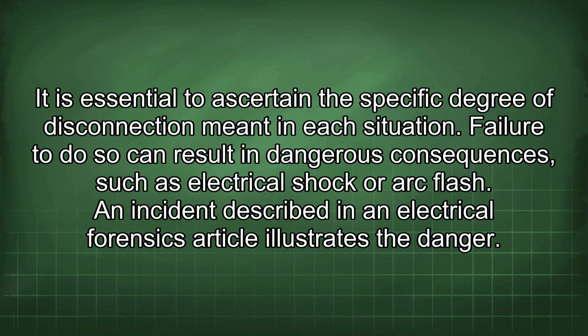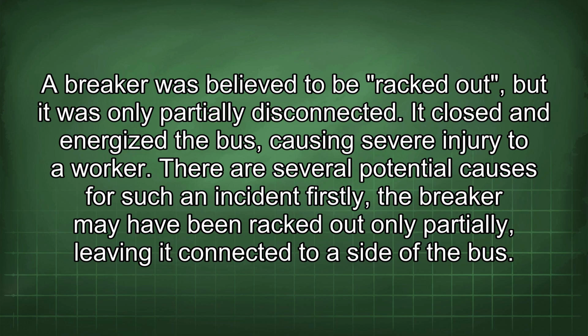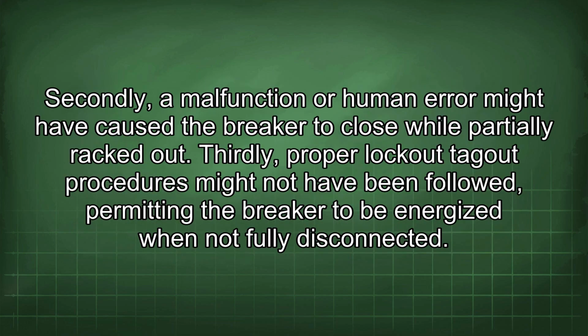An incident described in an electrical forensics article illustrates the danger. A breaker was believed to be racked out, but it was only partially disconnected. It closed and energized the bus, causing severe injury to a worker. There are several potential causes for such an incident. Firstly, the breaker may have been racked out only partially, leaving it connected to a side of the bus. Secondly, a malfunction or human error might have caused the breaker to close while partially racked out. Thirdly, proper lockout-tagout procedures might not have been followed, permitting the breaker to be energized when not fully disconnected.